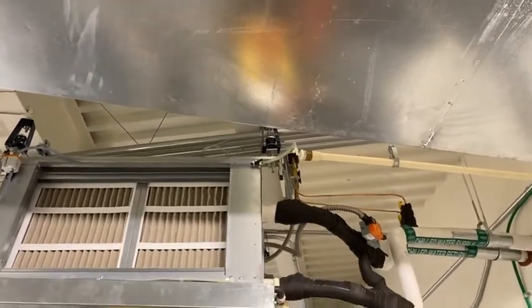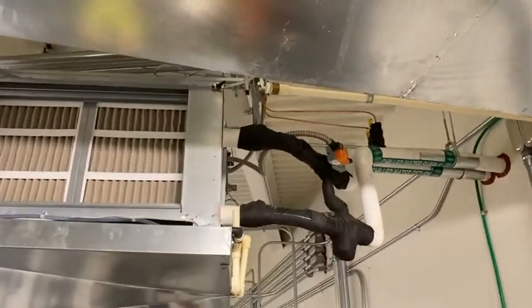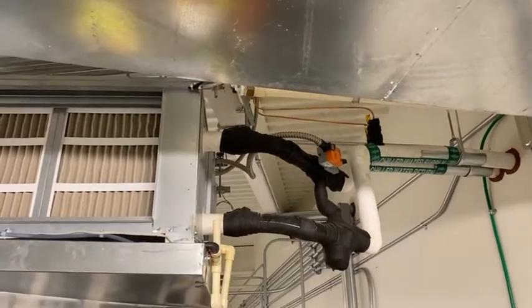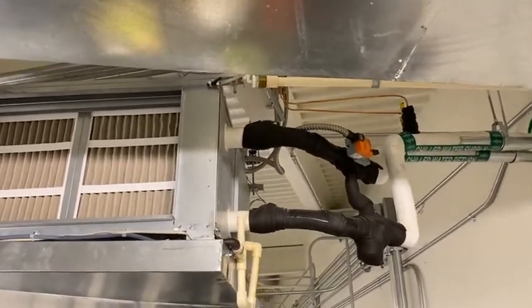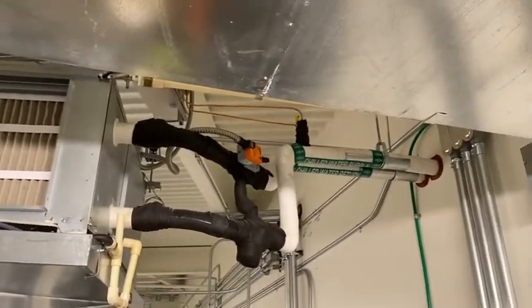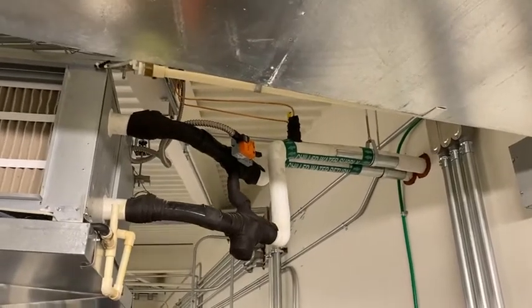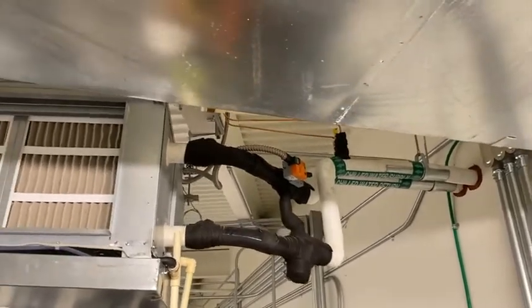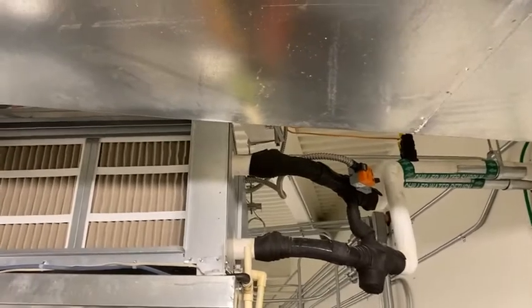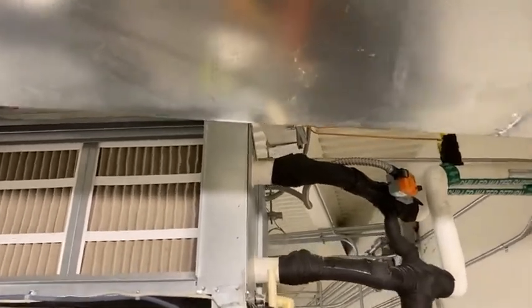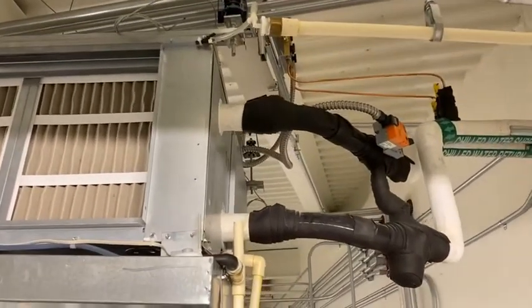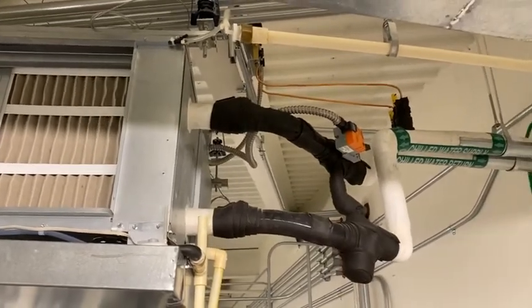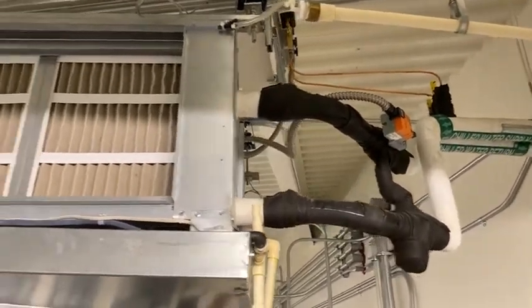I see that. Make sure that stays on, okay? If the pump stops pumping, it'll allow water to build up in the float reservoir and make the alarm switch. Okay? Without that, it'll spill out of the pan and it'll make a mess. Okay? I noticed that you got a drip pan for the roof drain. Yeah. But yeah, you got the outlet on top of the panel.